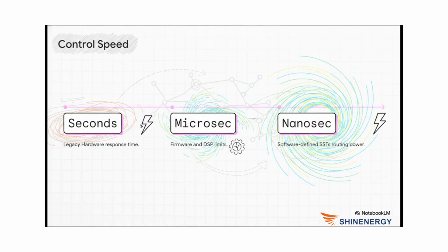Managing those aggressive AI power spikes requires lightning-fast response times. Legacy hardware reacts in seconds. Older digital signal processors or firmware-based controls might get you down to a few microseconds, but they quickly hit a computational wall. With a fully software-defined SST, you are suddenly routing and controlling massive amounts of power in the nanosecond range. That's billionths of a second.